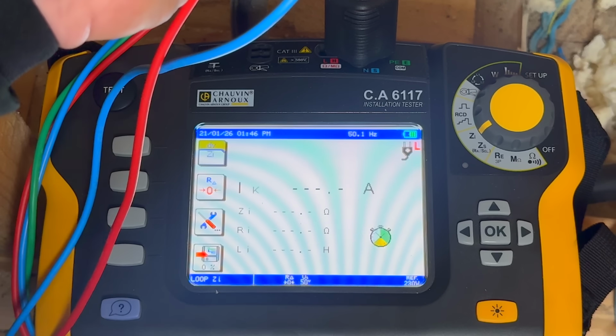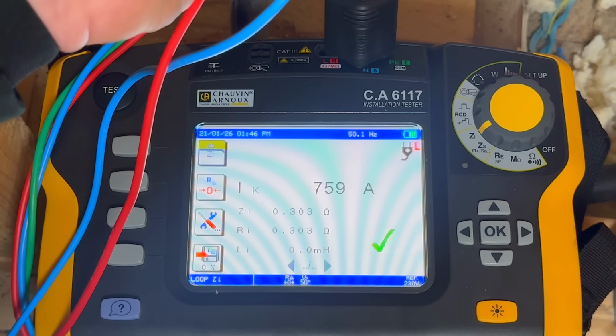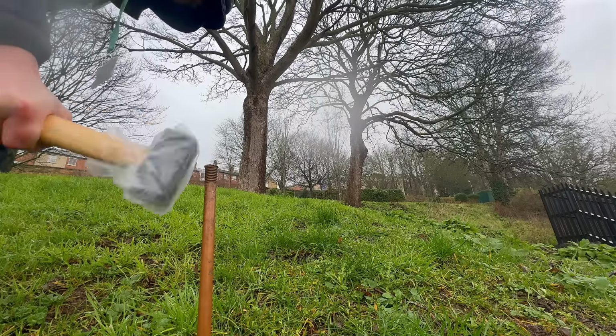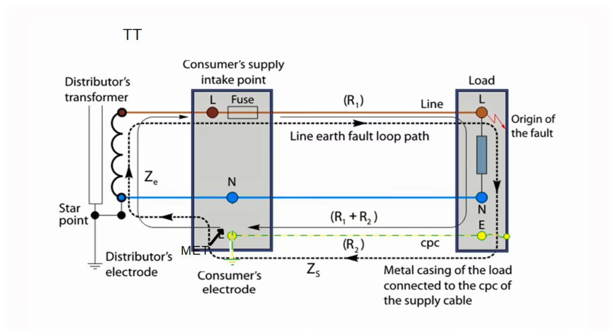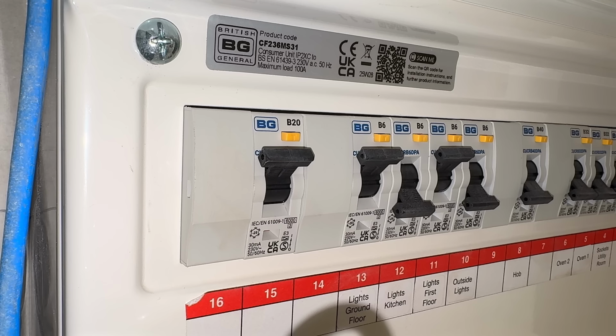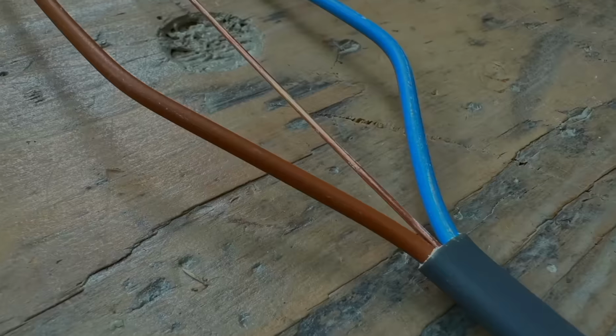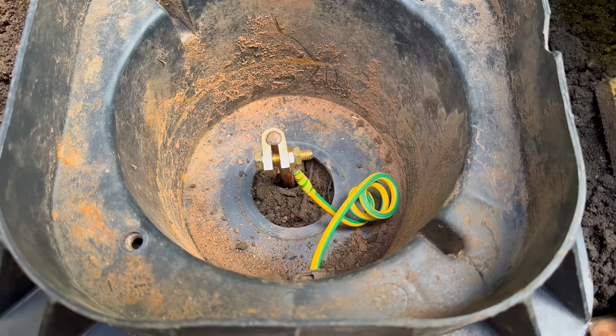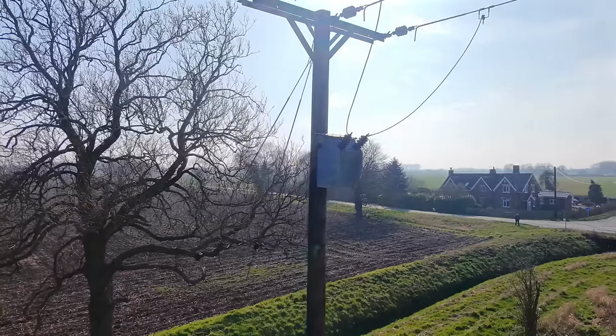Earth fault loop impedance testing answers a different question to earth electrode resistance testing. Earth electrode testing tells us how well it's connected to the ground. Loop testing tells us that the fault path is complete and good enough, so that the protective device will operate in time. On a TT system, that fault path can be long. It includes the line conductor, the protective conductor, the earthing conductor, the earth electrode at the installation, the earth electrode at the source, and the soil in between. So the earth fault loop impedance values on a TT system will always be higher than on a TN system, and that is to be expected. It isn't about how low the numbers are, but whether those protective devices will operate in time.